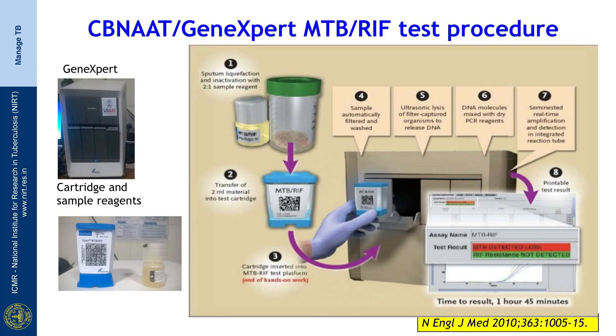This cartoon shows the actual procedure followed for GeneXpert detection. On the left side you can see the GeneXpert machine — this is a 4-module system. There are different machines which use either a 1-module, 4-module, or 16-module system. You can also see the cartridge being placed into these modules and the lysis buffer provided with the cartridge. The hands-on work required during this procedure is only 2 minutes, during which the sample is added to the container, and then the buffer is added in a 2:1 ratio.